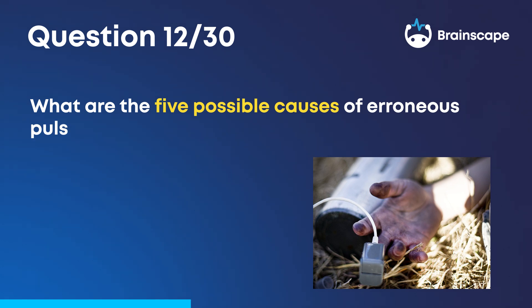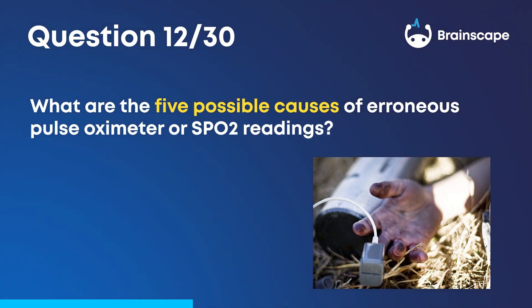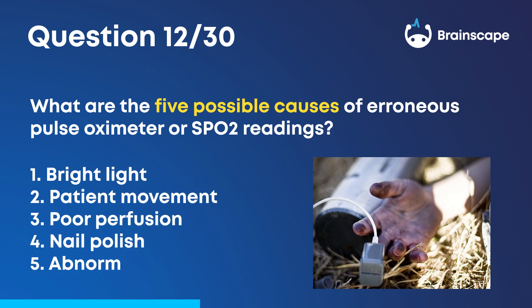Question 12. What are the five possible causes of erroneous pulse oximeter, or SpO2 readings? Bright light, patient movement, poor perfusion, nail polish, and abnormal hemoglobin.